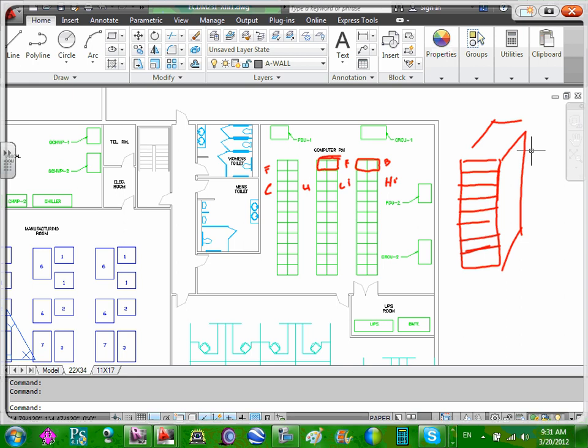What we're also seeing today, with this kind of construction, is that typically 5 to 10 kW might exist in this rack, but we're seeing racks today of 12 to 20, and even they could be greater than that. kW within a 2 foot by 4 foot rack. That's becoming a lot of power within this rack.